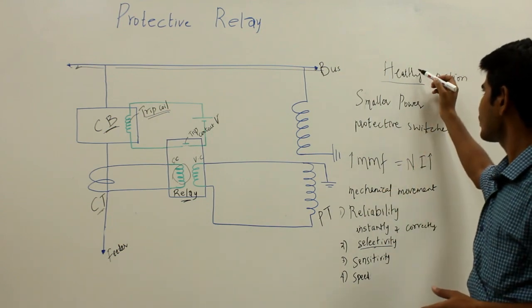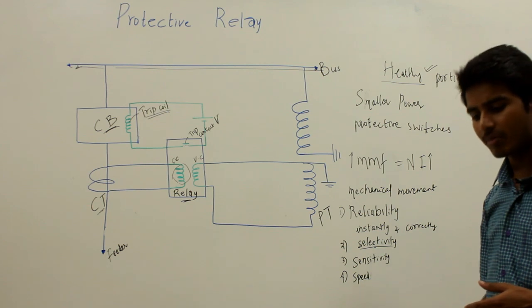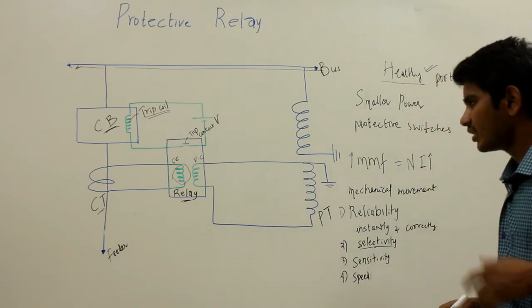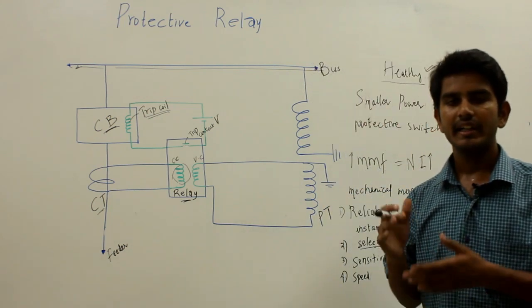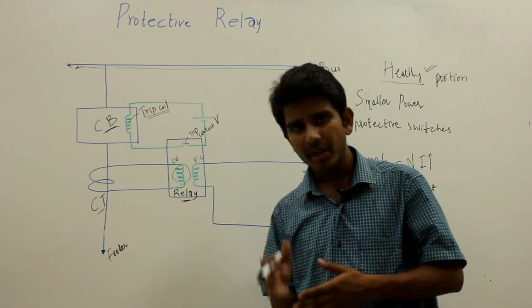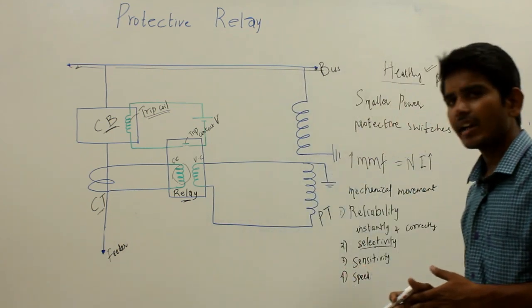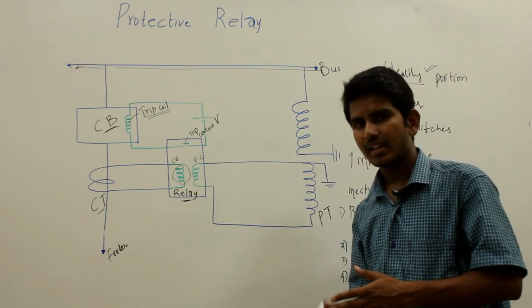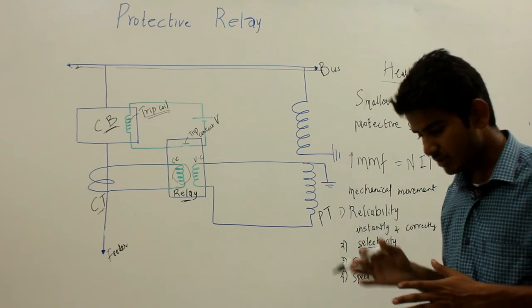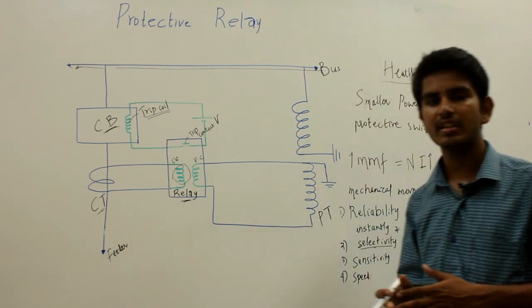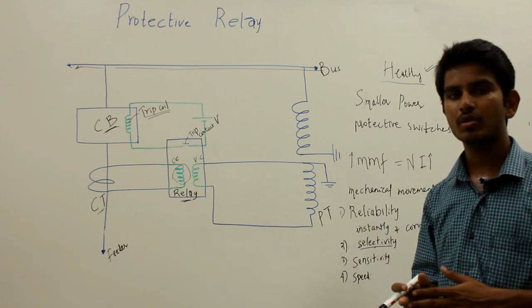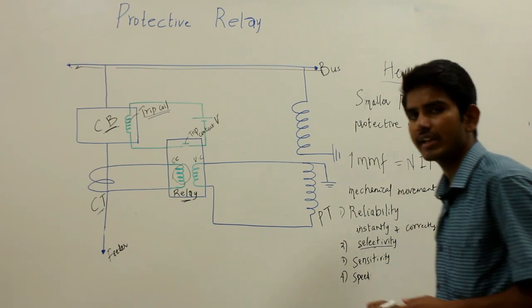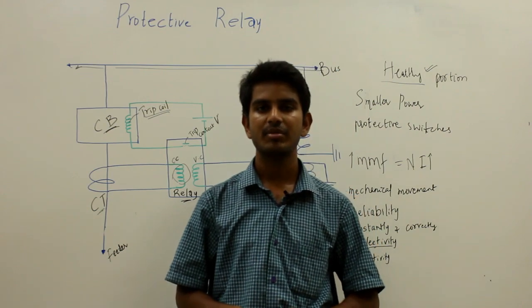If the relays associated with the healthy portion operate first, it results in undesirable operation of the relays in the power system. Conversely, if the relays at the faulty portion do not operate in time due to some defect, the relay associated with the next healthy portion should operate as backup and isolate the faulty portion. So the relays should not be so fast as to cause undesirable operation, nor so slow as to cause damage to equipment. This is the operational principle and the functional requirements of the protective relay used in power system protection.